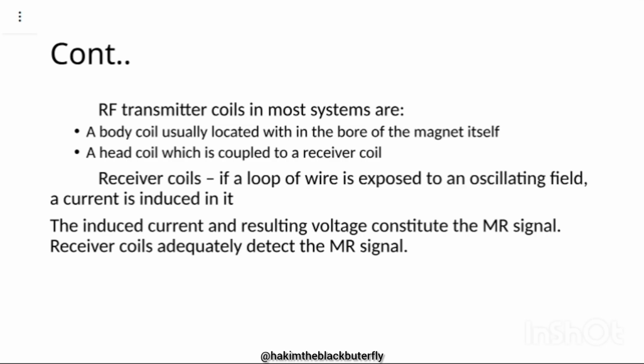Then RF transmitter coils, in most cases, are the body coil, usually located within the bore of the magnet itself. These only transmit. Then a head coil is coupled to a receiver coil. So if you're using a body coil, in most cases it is a transmitter, so it will transmit the RF, but there will be another coil available to pick up that particular signal.